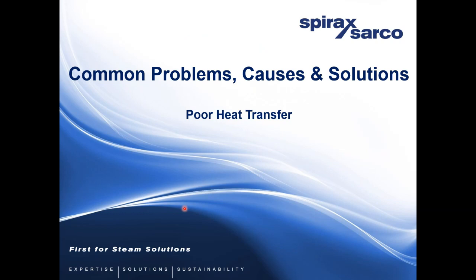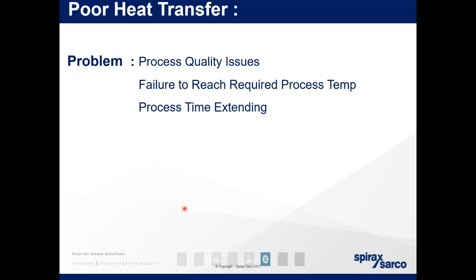Yeah. So common problems, causes and solutions, this time for poor heat transfer. So the problem, what you will see on site: process quality issues, failure to reach required process temperatures, process time extending. So if we think of that cooking vessel, as we were saying, temperature not reaching the required temperature means that the product can spoil. If it does reach it but takes longer to get there, it means that the cooking time takes longer, therefore you're using more energy.